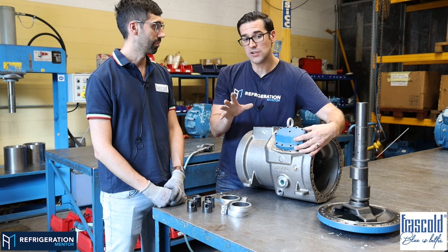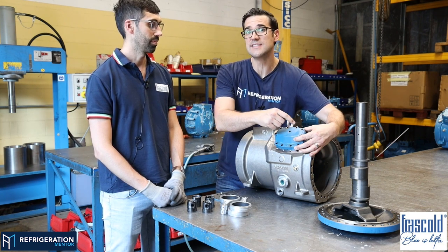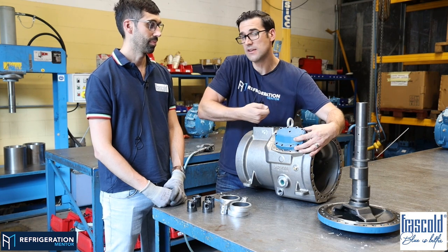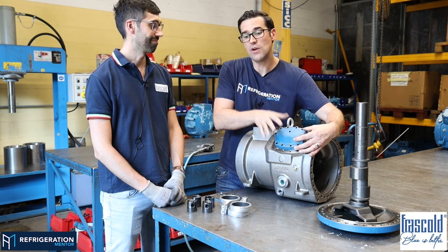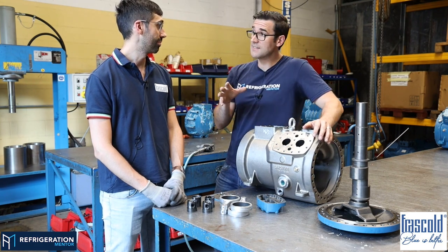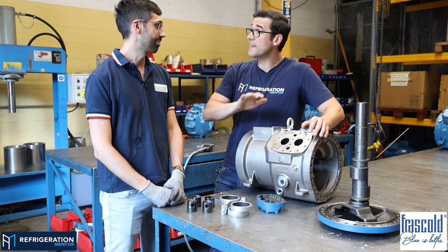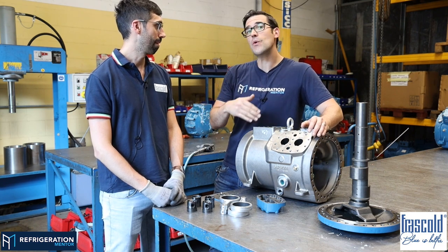After, what I do is I take my torque wrench and then I just go around and verify it is the exact torque once again, just because it'll click every time. So you have the proper torque, because what I've seen and what I've done in the past is I did not use a torque wrench and I just tightened them down way more than it should be. And that's where leaks can happen.